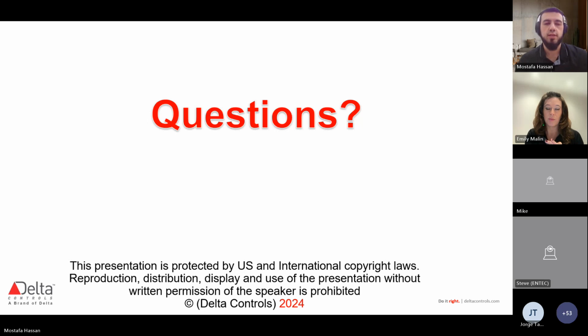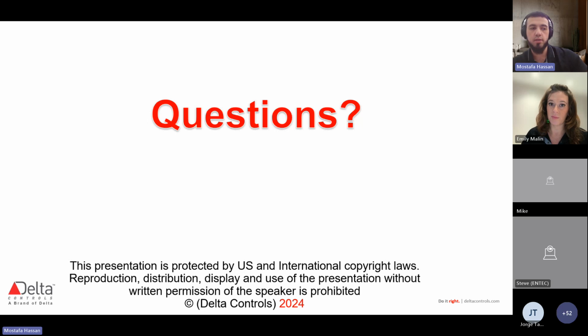That's a loaded question, and it has to do with what you're trying to achieve for your customer. There isn't one document out there that will tell you if the building is actually returning on investment properly. But the best way to do that is probably to partner with an engineer who's doing energy auditing. I've heard of scenarios where vendors work with an engineer to do energy auditing on the building and figure out what the building needs, and what the building automation costs, or what is actually needed to get the building to where it needs to be. Then we look at the cost spent versus the energy savings over the next couple of years until you get that return on investment. That's really the first step. But again, there isn't a standard document out there. There probably are several of them.